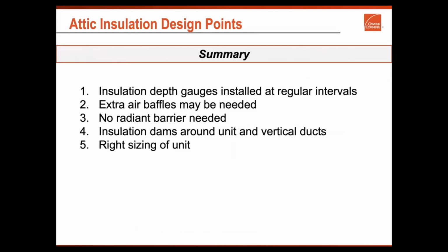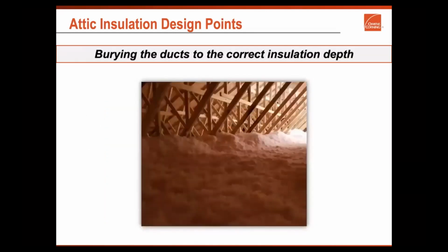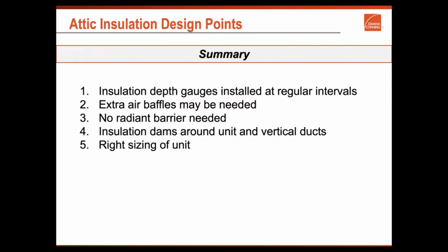And on this, we want to make sure we have depth gauges. As you can see in this previous picture, we don't have any depth gauges, but you can tell where the trunk is. Extra baffles are needed, no radiant barrier. Currently, that's kind of what we're sticking to. We will be testing radiant barriers this year, hopefully, if not next year, and seeing how much they actually affect possible condensation on ducts, both R13 and R8 ducts, and insulation dams around the units.